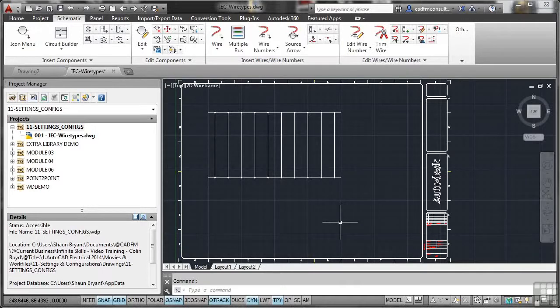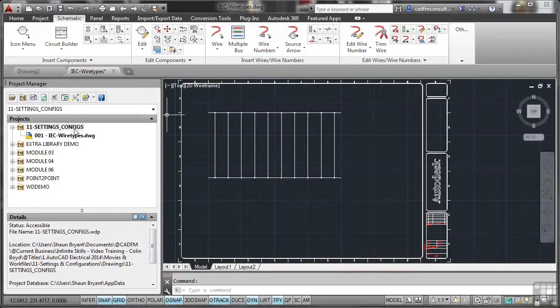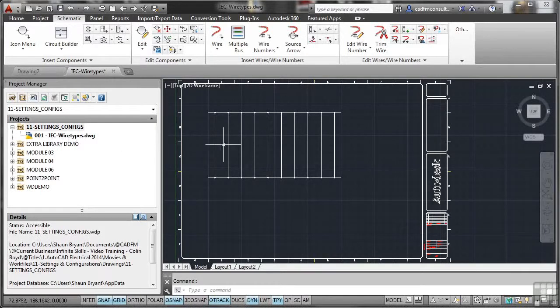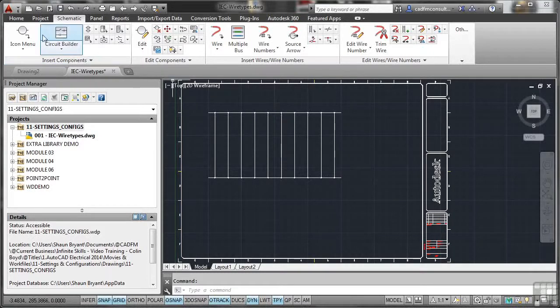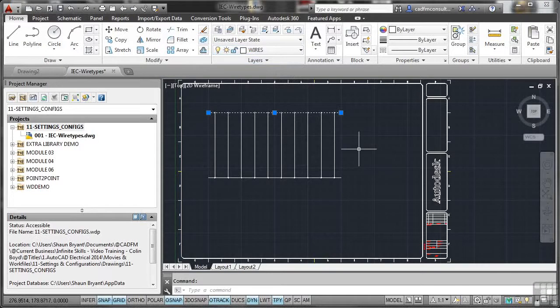We're now going to look at wire types in our drawing. What I've done is created a drawing called IEC wire types and put it into our AutoCAD Electrical project, which is 11 settings configs. There it is — sheet 001, IEC wire types. We're running with the IEC standard, which is the European metric standard. I've put a standard wiring ladder into the drawing. If you go to the home tab on the ribbon and select one of these wires, you'll see they're on the wires layer — I've deliberately put them there.